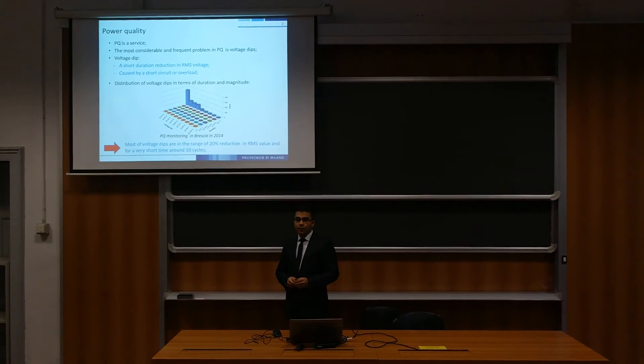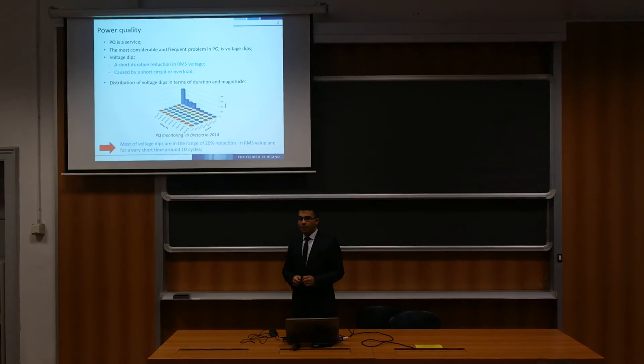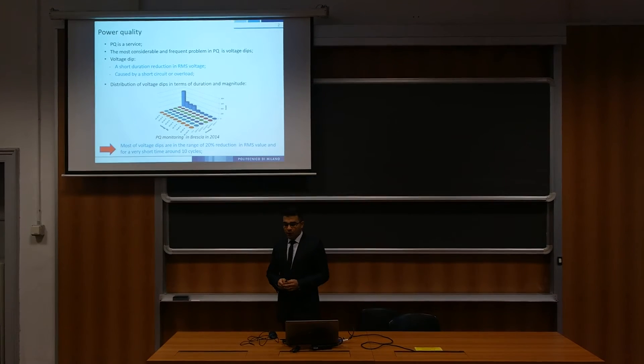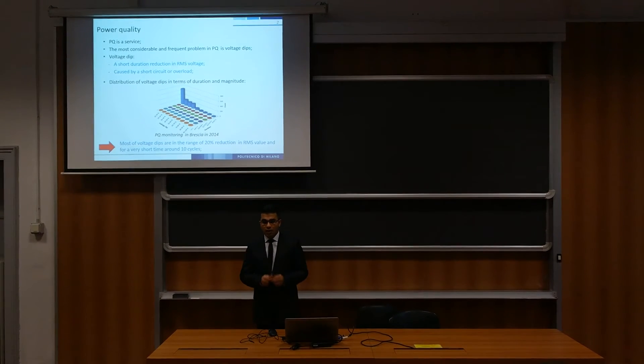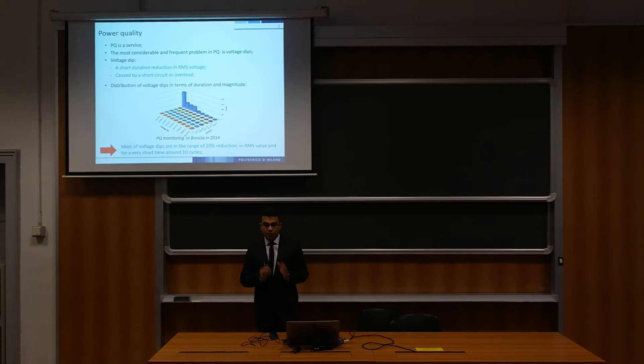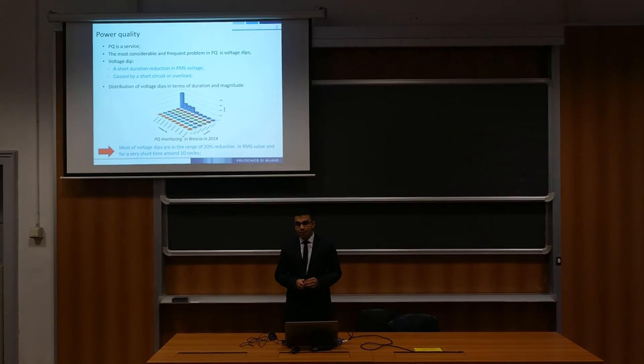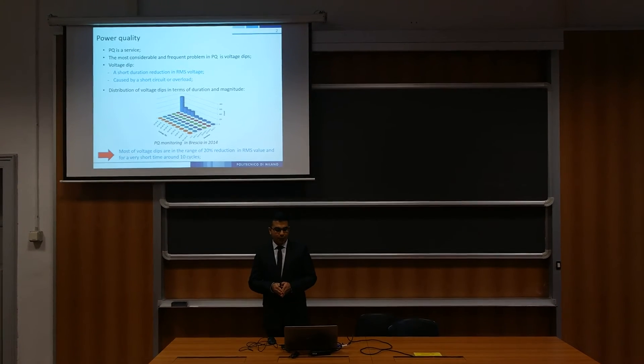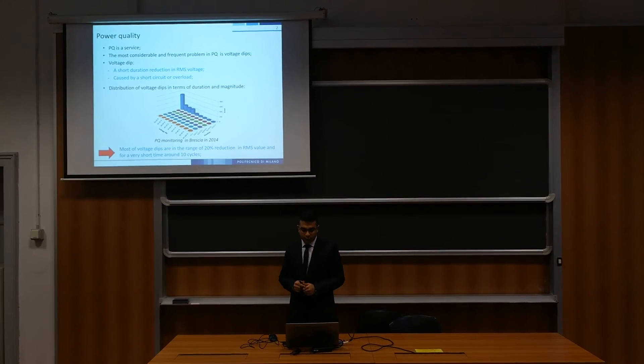The most considerable and frequent problem in the field of power quality is voltage dip. Voltage dip is a short-duration reduction in RMS value of the voltage in the range of 10 to 90%, which is the main result of short circuit, overload, or even inrush current of big motors.